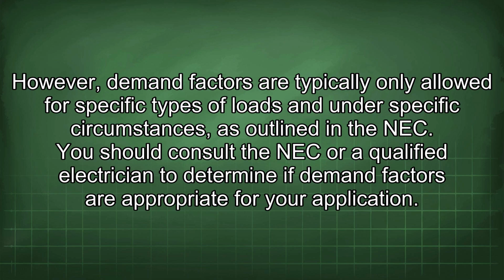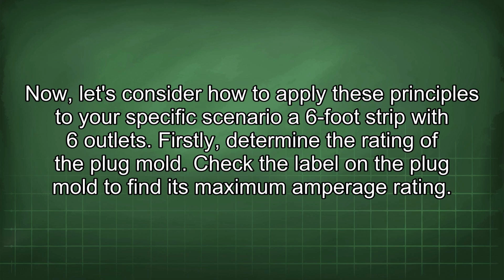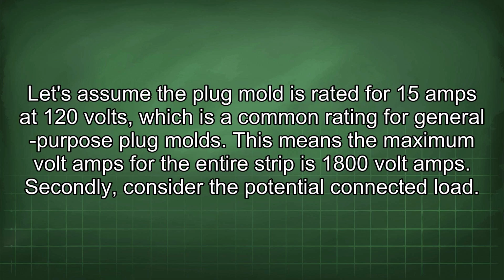Now, let's consider how to apply these principles to your specific scenario: a 6-foot strip with 6 outlets. Firstly, determine the rating of the plug mold. Check the label on the plug mold to find its maximum amperage rating. Let's assume the plug mold is rated for 15 amps at 120 volts, which is a common rating for general-purpose plug molds. This means the maximum voltamps for the entire strip is 1800 volt amps.